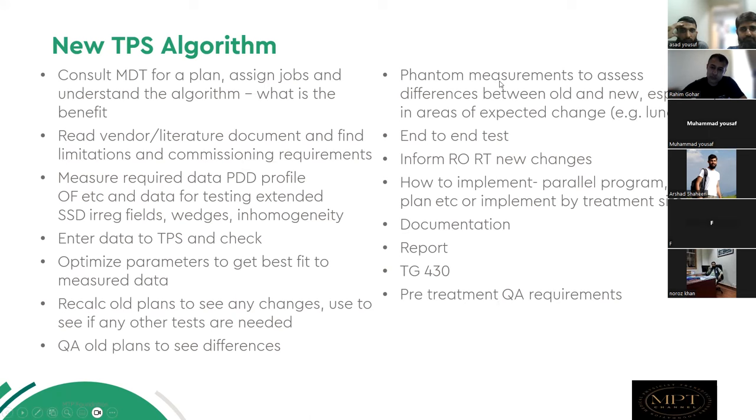And then you said you can do some phantom measurements by simply creating a water phantom and see that it is picking the right doses, and then you can introduce your inhomogeneities. And Asad said, this is very crucial. You have to do end-to-end.